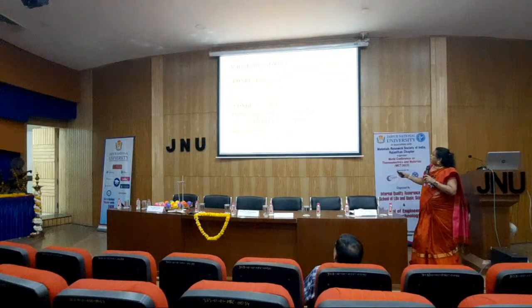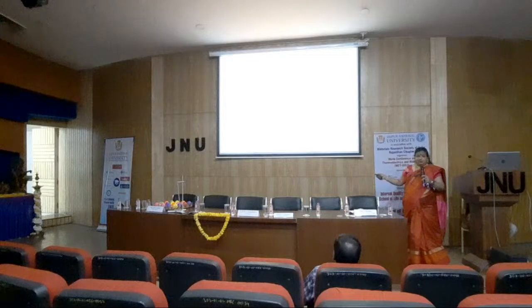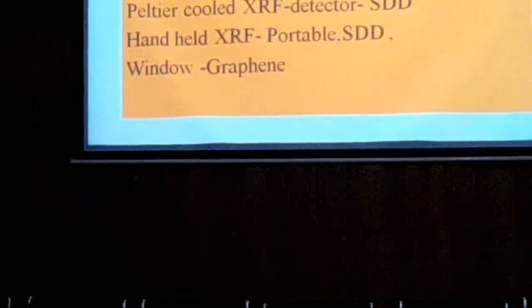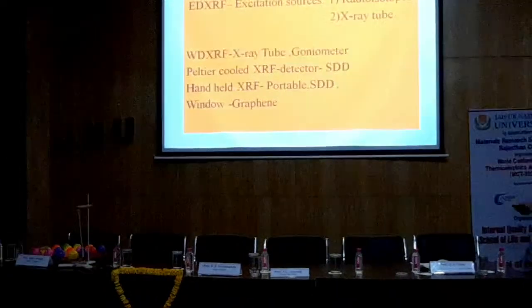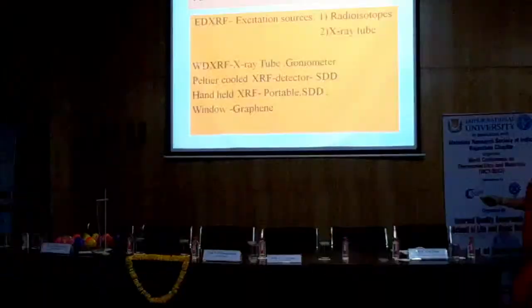Next. Okay. So variations, as I told you before, you have excitation source, radioisotope, X-ray tube. WD, we have wavelength, goniometer, tube, Peltier cooled X-ray detector, SDD. Now Peltier cooling avoids the liquid nitrogen filling, a thermoelectric property. So it is suitable. I can refer to the topic of this conference which talks about thermoelectric. So with that principle, you have the Peltier. I worked with all this except the WD.